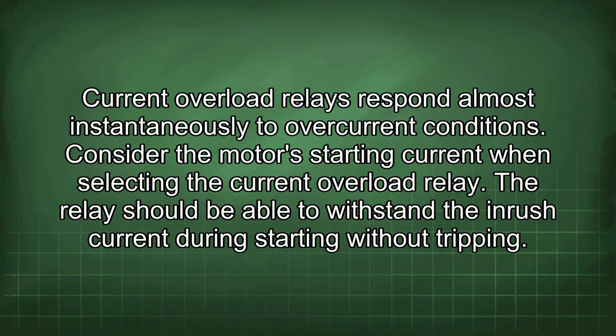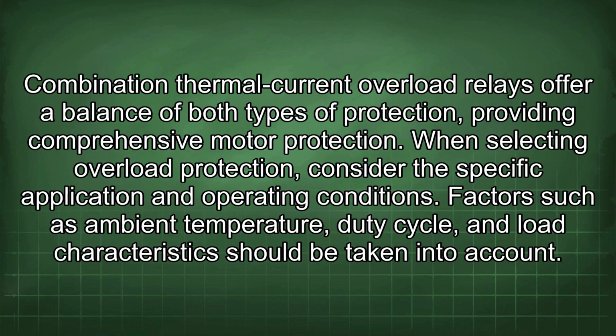Current overload relays respond almost instantaneously to overcurrent conditions. Consider the motor's starting current when selecting the current overload relay. The relay should be able to withstand the inrush current during starting without tripping. Combination thermal current overload relays offer a balance of both types of protection, providing comprehensive motor protection.